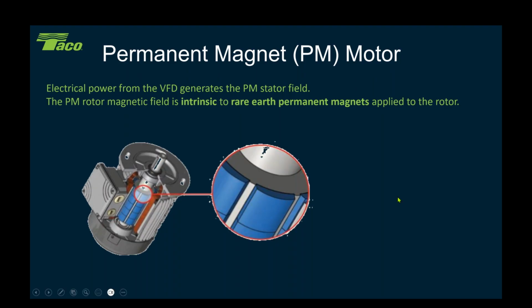Okay, when we move into the realm of permanent magnet motors, what we do is we take the conventional rotor out of the motor, and we take the copper and the steel and everything off of it, and we mount rare earth permanent magnets to the rotor. Okay, they're encased in epoxy, and they're epoxied to the rotor with a high strength epoxy, and that creates a permanently magnetized rotor. Okay, so now all we have to do is create the stator field with our VFD. And now because the rotor is permanently magnetized, we don't have to waste any energy in creating that second magnetic field inside the rotor.